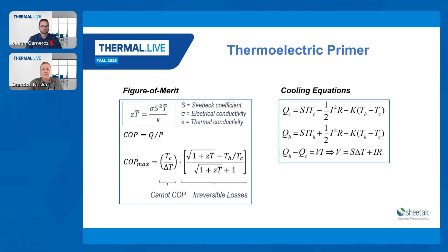And so your thermal system, whatever that may be, as Sean mentioned, we're obviously not trying to eliminate air cooling or liquid cooling, but whatever your thermal management system is, if you implement a thermoelectric cooler, it has to handle the load that you're cooling plus the extra load that the thermoelectric device creates itself.